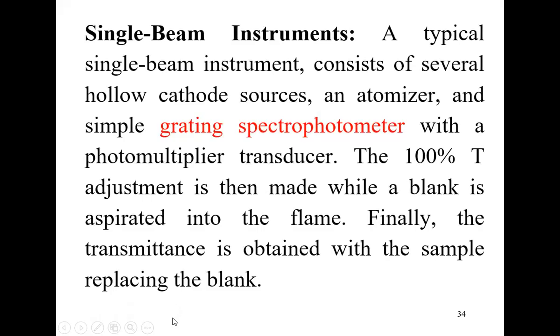So that is the electrode-less discharge lamp. Now I want to get here before I stop on, remember, radiation source and the instrument, the single beam instrument, a typical single beam instrument. Usually, you know how a typical beam spectrophotometer works. Remember, it does not have a reference. It does not have a reference. You put the same spot. You can do first your blank, remove your blank, and then put your sample there again.